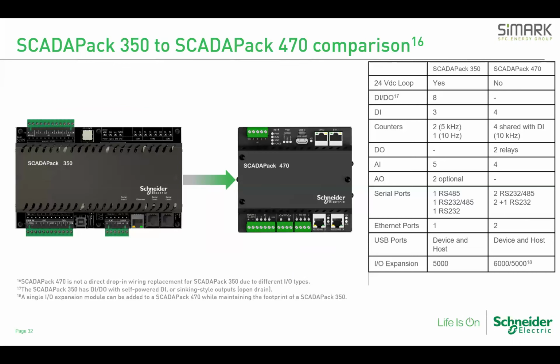The 350 to 470 is compared here. You can see the difference is that we're not supporting the capabilities of the 350 to support a 24-volt DC loop from the RTU here. So powering of analog inputs would need to be done separately if using the 470 compared to the 350 RTU. But the nice thing about the 470 is that you are able to put in some extra expansion modules if necessary, but it's not intended to be a drop-in wiring replacement for this particular RTU.